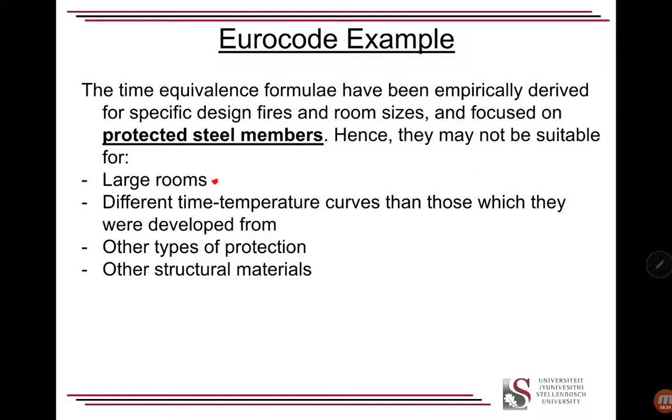And they may not be suitable for large rooms where the fire dynamics behavior is different, different time-temperature curves than those which where they were developed from. So if we have longer cooler fires or shorter hotter fires, they may be less accurate. Other types of protection than sort of used in the experimental tests, and other structural materials. And even a concrete section, for instance, if we've got a concrete beam here with rebar in the top and rebar in the bottom.